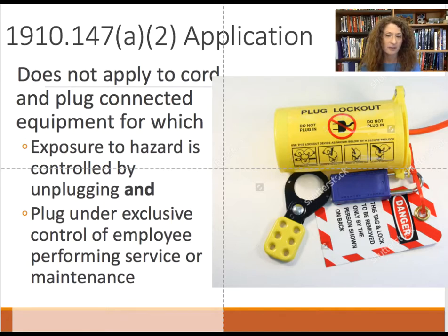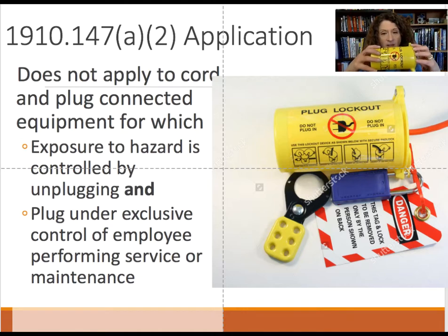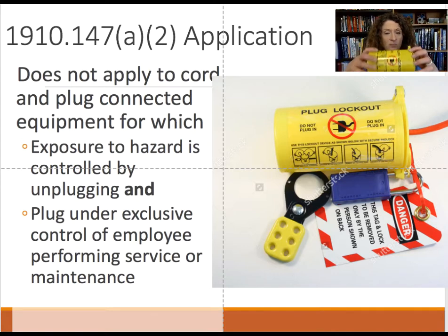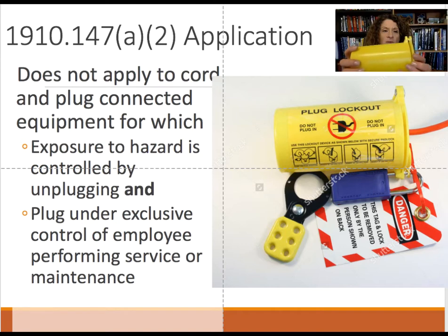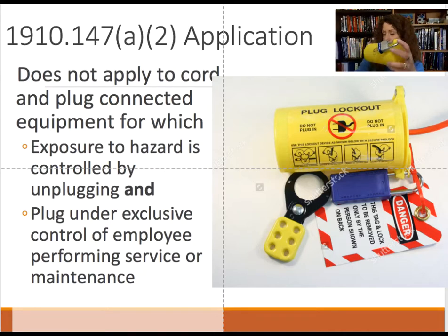Lockout-tagout does not apply to a plug if pulling it completely turns the equipment off — you don't necessarily have to lock it out. However, lockout devices exist for plugs so that someone doesn't accidentally plug it back in and turn it on. It is highly recommended to lock out and tag out equipment if you're not close enough to monitor exposure. You place the lockout device over the plug, put a lock in place, and it's locked out and tagged out.